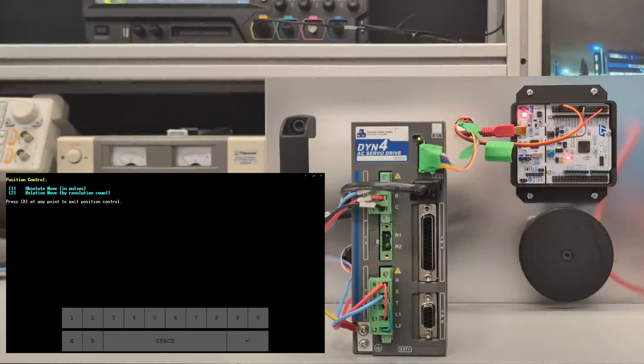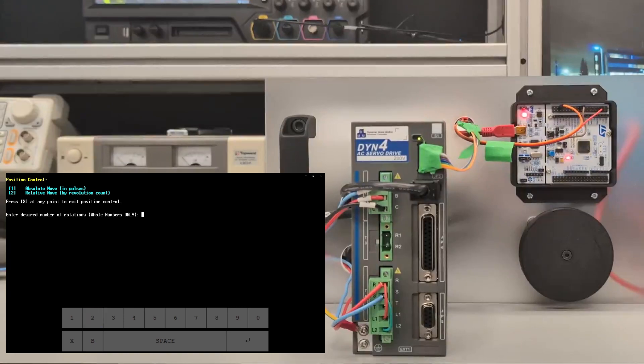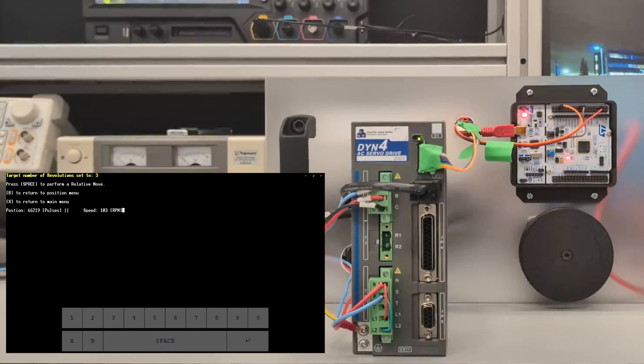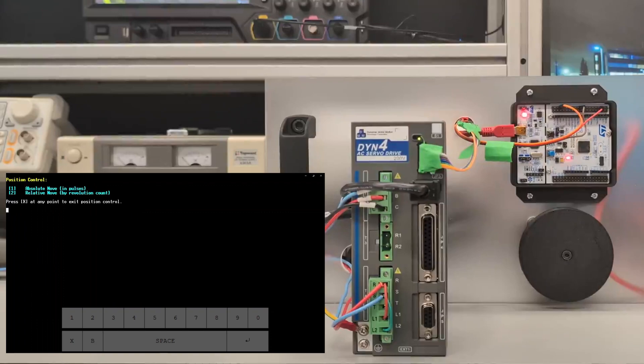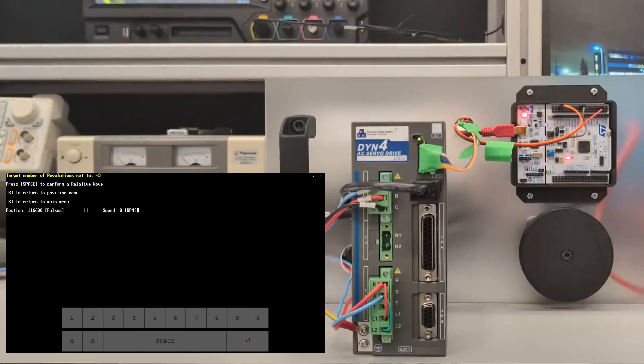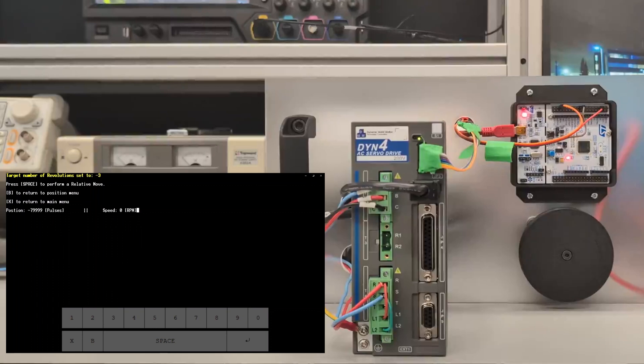You'll see in just a minute here that it will stop right at negative 80,000. We're going to try the relative move now. This will only take whole numbers for rotations, but this could be modified if you desire. We're going to try three revolutions, and just to prove to you that was three revolutions, we're going to do negative three revolutions so that we get back to that original negative 80,000 pulses. As you can see, we are back at negative 80,000.